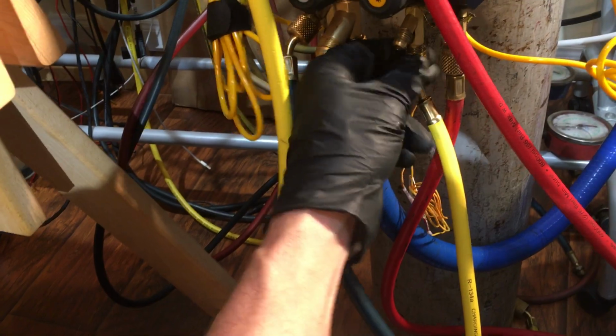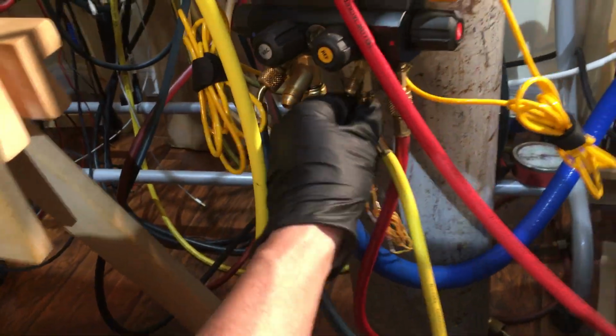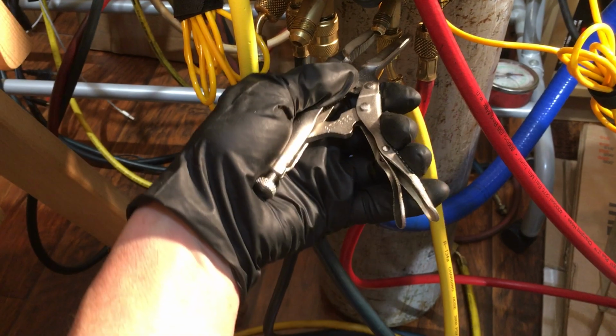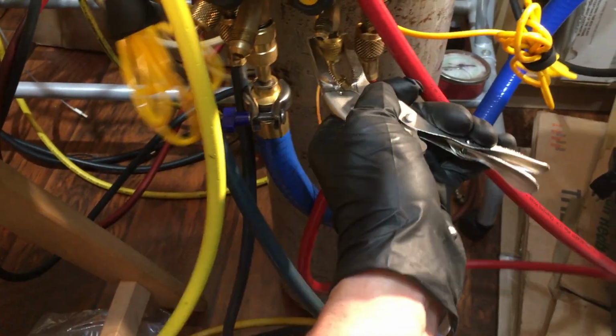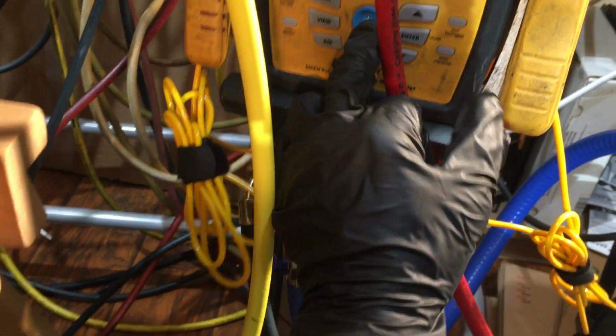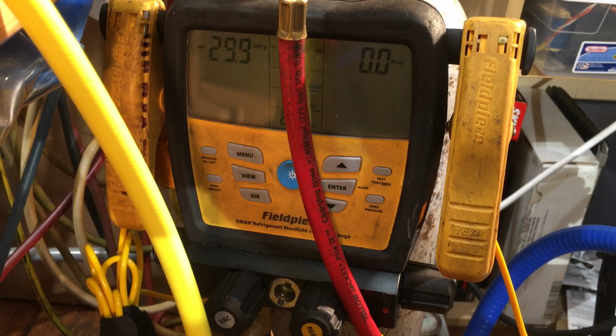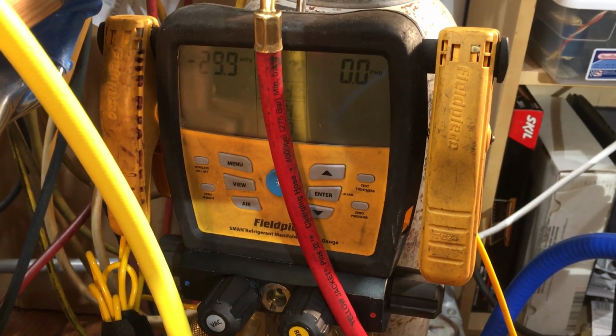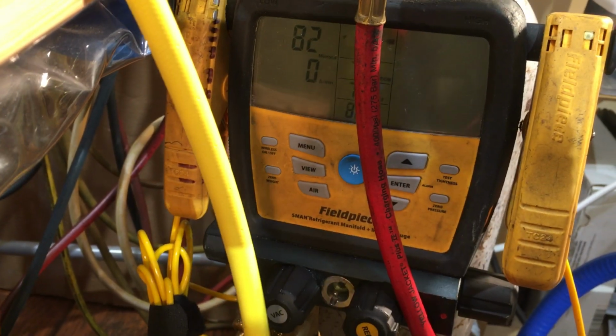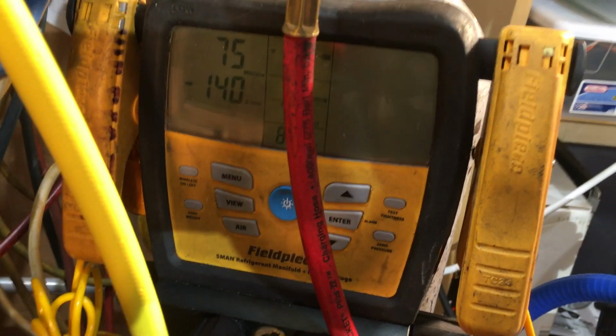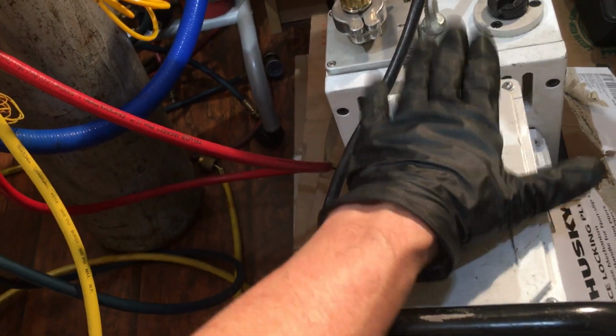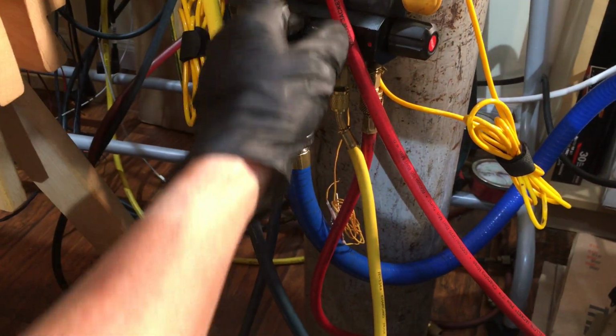And since I know those white seals are really bad and you can't seal them really well with your hand because they're such garbage, I will give them the nice tool treatment with a little extra squeeze. And let's turn back on our gauges. And we're at under 80 microns. We're going through the silicone hose to the 12 CFM pump that's capable of going down to 3 microns. And you read vacuum in microns, not inches. Since there's no education in the automotive field and it's not required, they don't know that. But this is something you have to learn.